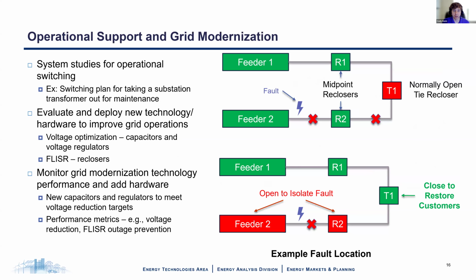All right. And then the last piece, engineers are also operations support and help engage in grid modernization. That's the subheading for my title, grid mod. So this is an area I do a lot of work in. What does that actually mean? On the operations side, a lot of times you're doing studies for switching to see if certain types of reconfiguration on the system are practical. So if we need to take a substation transformer out of service for maintenance, how do we restore all of the customers that are normally served by that station? And can we pick them up from other places? That's a switching study that a planning engineer might do on behalf of operations.